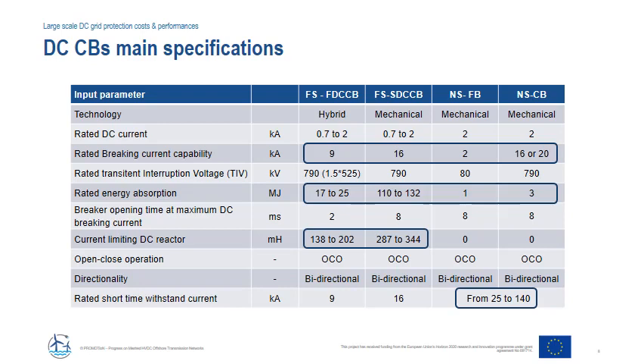For non-selective strategies, it can be observed that some DC circuit breakers would have to withstand potentially very high short-time currents. These currents are mainly due to the discharge of several cables in the fault and could lead to some technical limitation for the DC circuit breaker technology. As such, this could be a limitation of these strategies. However, these currents are more a question of topology design than related to the size of the DC grid. Solutions to limit this current would have to be proposed if required.